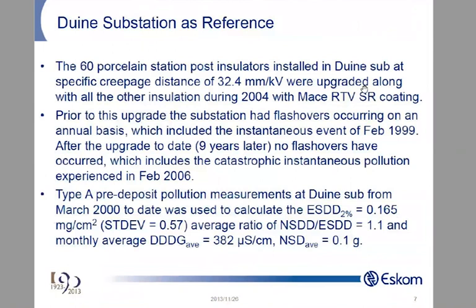Okay, so what we do is we take 60 porcelain station posts in the substation. We know their performance, we know their creepage distance, and we know what happened to them during and after the event, the big instantaneous pollution event.